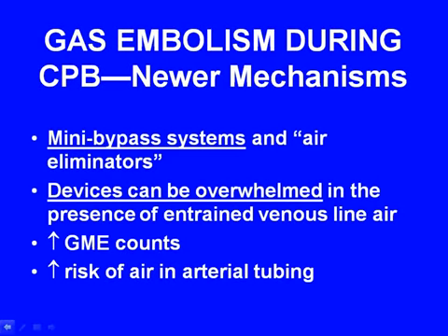Air embolism using mini bypass systems have also been implicated in air embolism. As you may know, many of these mini bypass systems have no venous reservoir, and the transit times of blood through the extracorporeal circuit is quite rapid.